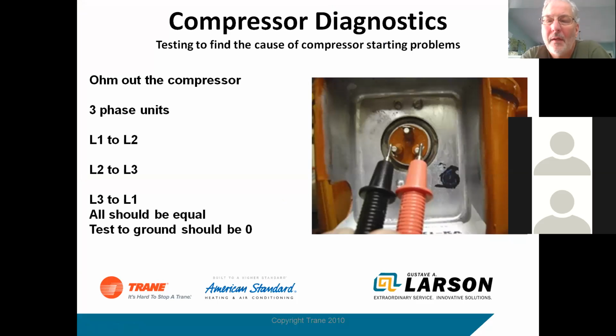All right. So what I want to do is talk about 3-phase compressors, and they look similar. The pins look almost the same. The difference is they're equal resistance. So when you're ohming out a three-phase compressor, you've got L1 to L2, L2 to L3, and then L3 to L1. And you take that ohm value, and that should be plus or minus 2%. I mean, if it's 1 ohm, 1 ohm, and 1 ohm, it should be like 0.9 to 1 ohm, maybe 1.1 at the most.